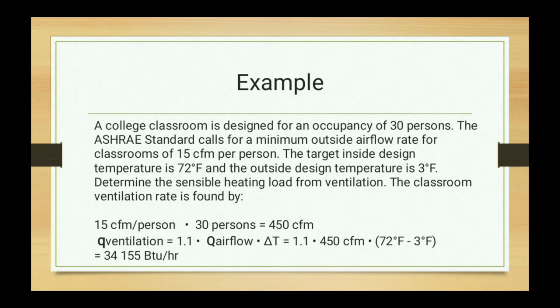So, gamitin natin yung formula kanina. Yung ventilation is equal to 1.1 multiplied by airflow multiplied by delta T. So, magiging ganito: 1.1 multiplied by airflow. Ano ba airflow niya? Ayun, yung 450 cubic feet per minute, multiplied by the delta T, yung temperature niya. Yung 72 degrees Fahrenheit, yun yung inside temperature, minus the outside temperature, 3 degrees Fahrenheit. So, it is equal siya sa 34,155 British thermal units per hour. So, yun lang po.